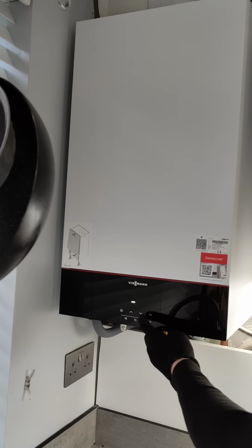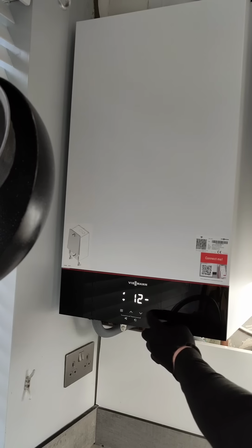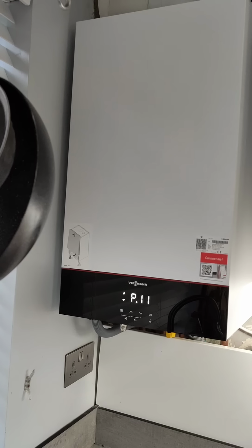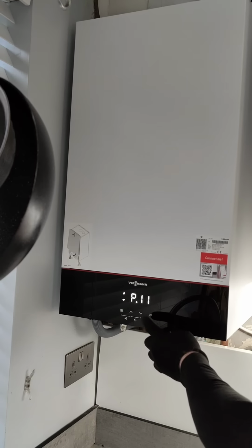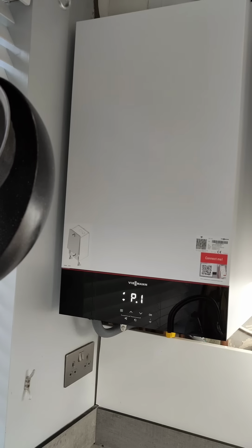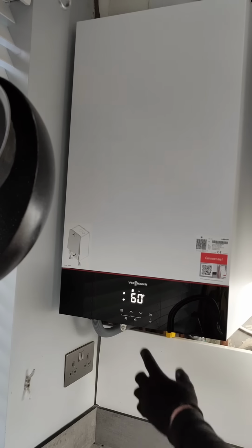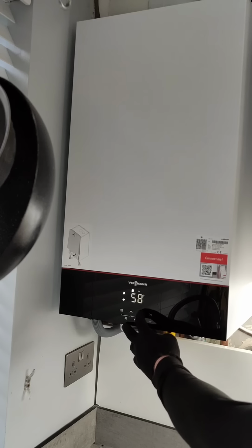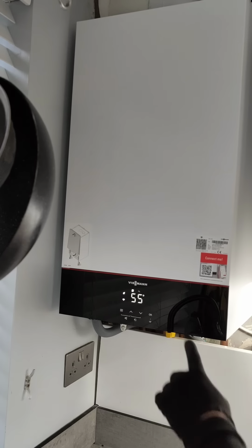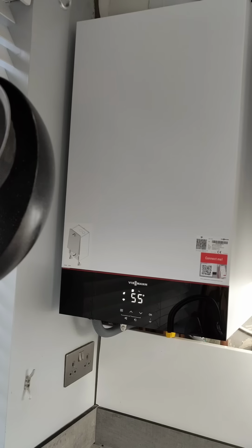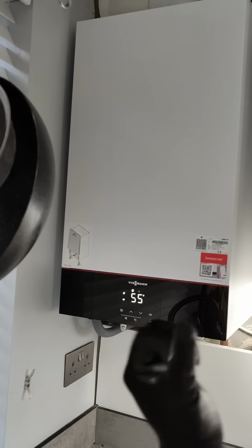And then P10 is if we want to set the date, so it's 23rd of the 12th, 21. And P11 is if we want to set the time, it's now 4:04. So now we've disconnected the weather comp, so if we just use the up and down arrows we can set the temperature of the radiators. The higher this number is, the more heat we're going to lose out of the flue, and the less the boiler is going to recover that heat by condensing.